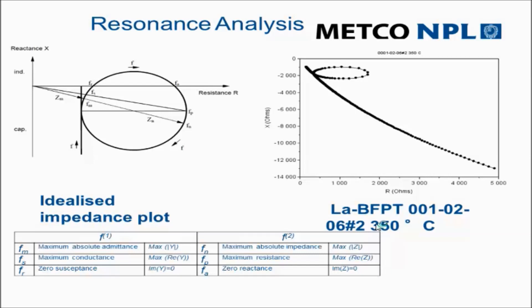This side shows an actual measured frequency sweep at 350°C, with resistance on one axis and reactance on the other. You can see it is a long way from the ideal measurement. One of the difficulties, particularly at higher temperatures, is getting the crossing of the x-axis. There's an offset here — even though you compensate for stray inductances and stray capacitances when you set up the measurement, there's a limit to how effective that compensation is, and at some point it's going to have an influence.